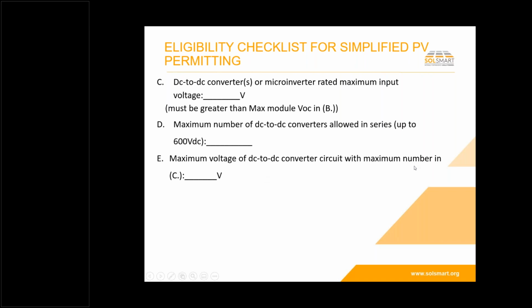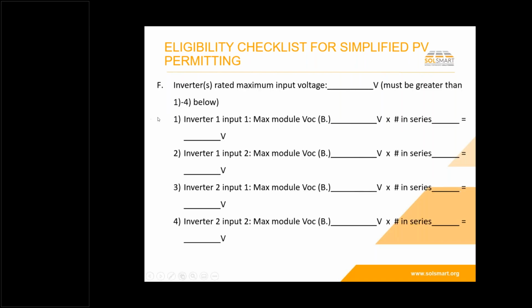And then the maximum voltage with the maximum number in circuit, that's usually controlled by the inverter. It might be 380 volts or something like that. If we're running modules directly into inverters, then we will be putting them in series, and so we run through this voltage calculation here, and this allows for multiple inverter inputs and multiple inverters, and we'd fill in, depending on how many inverter inputs we have and how many inverters we have and all that. Now, when I say we, I mean the installer, the contractor is going to fill this out. The local jurisdiction is just seeing that the ratings are filled in and they're within the ratings of the equipment.